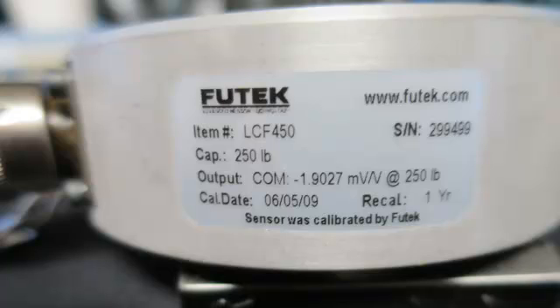To determine the maximum output signal, simply multiply the sensitivity times the excitation voltage. I will use these values a little later to scale the data to pounds.